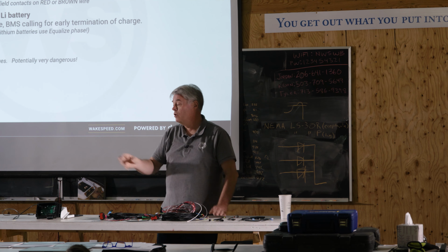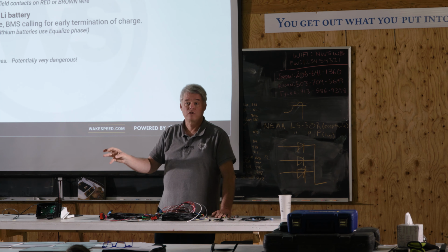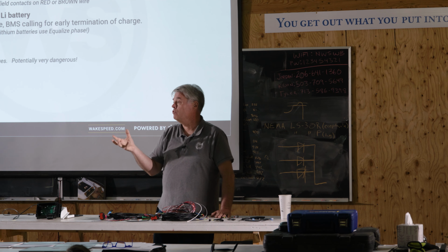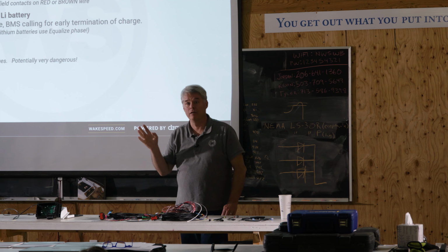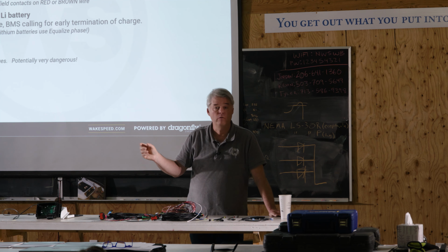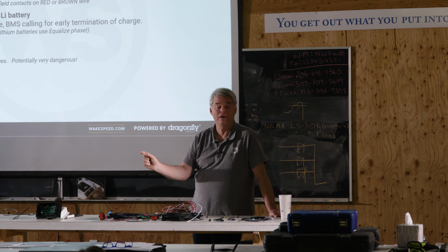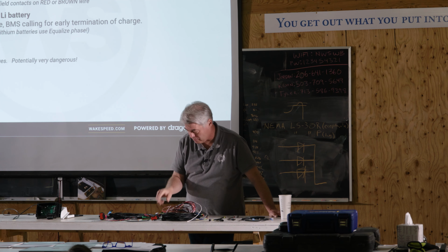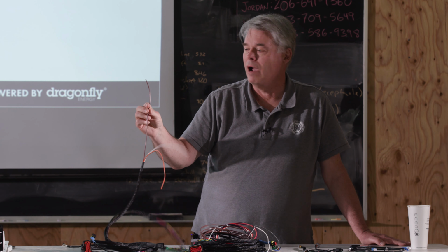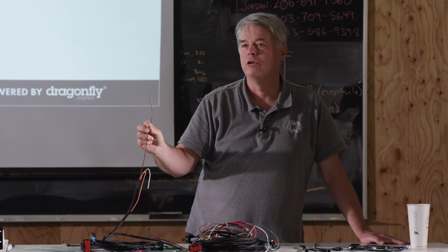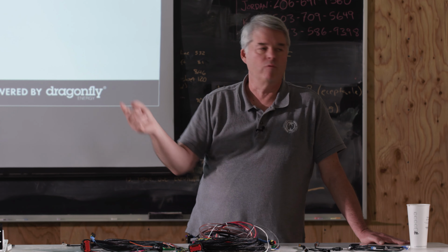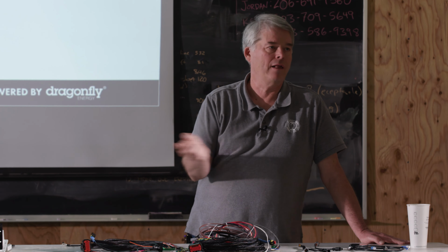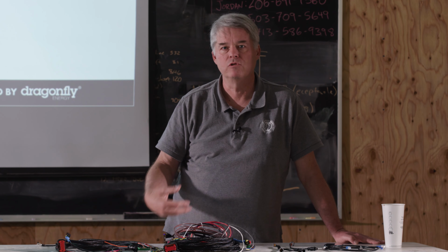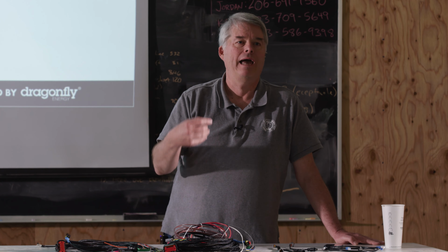The solution is, don't open that service disconnect switch - hide it somewhere. Another thing you can do, and I know this is very common in the marine industry, you can get those service switches with auxiliary contacts, little smaller ones. Route the brown wire - where's my brown wire? Route the brown wire through that service disconnect switch so that when the battery is disconnected, the regulator will also be depowered. That's actually a good solution for that approach as well. But these are the dangers of these newer systems that have to be thought through - hadn't been thought through what happens if the customer does that.